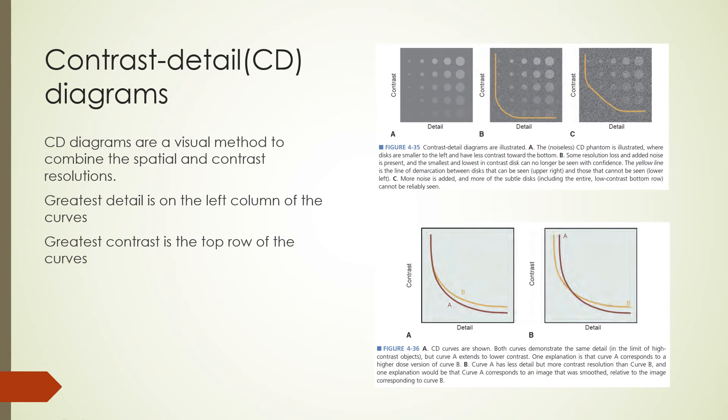In a previous lecture, we learned about spatial resolution and contrast resolution as if they were separate entities, but both of these quantities together are important on any given image. In particular, it does not matter if the imaging detector has excellent spatial resolution if there is too much noise in the detector and the statistical integrity of the image is not sufficient to detect a small object. We can understand the relationship between spatial and contrast resolution by using a conceptual visual method called a contrast detail diagram. A few contrast detail curves are shown on this slide. On the figures shown, greatest detail is on the left column of the curves and the greatest contrast is the top row of the curves.